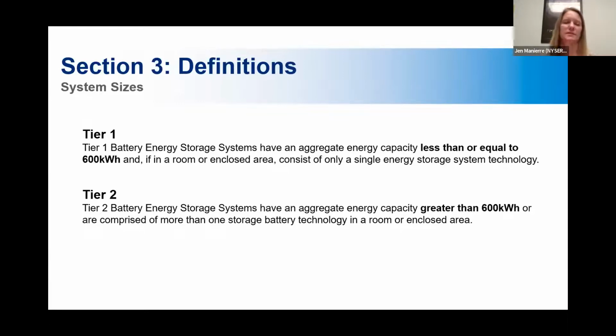So skipping right over into section 3, definitions. I think the two most important definitions in here are how we're dividing the storage systems up for their permitting requirements. Like I said, tier 1 is going to be those smaller systems. So they have an aggregate energy capacity less than or equal to 600 kilowatt hours. And if they're indoors in a room or enclosed area, they also have to be only a single energy storage system technology type. Tier 2 systems are either larger than 600 kilowatt hours, or if you're mixing more than one battery type in a room or enclosed area, we would consider that tier 2 as well, just in case, because you want to explore any potential interactions between the two chemistries.